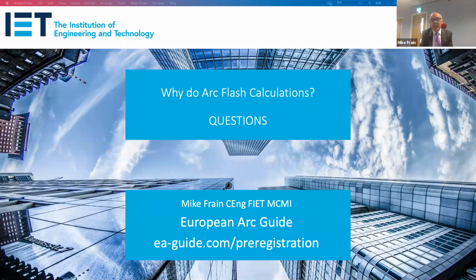Well, impedance affects arc flash calculations in exactly the same way as it does for shock protection. So impedance happens to be your enemy when it comes to arc flash protection. You might be saying, well, doesn't low impedance mean lots of current - what happened to I squared T? Well, I squared T still works, it's still there. But as I demonstrated earlier, if you reduce the current by a few amps sometimes, or perhaps more, the time to trip could be massively impacted. So you reduce the current, the I squared bit is not reduced that much, but then the T is through the roof.